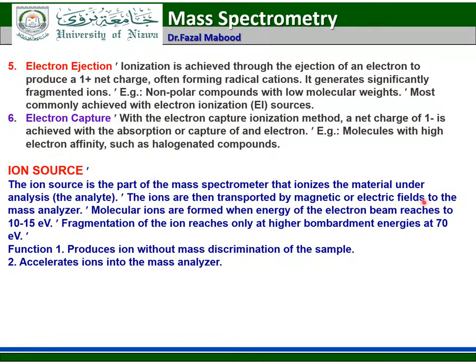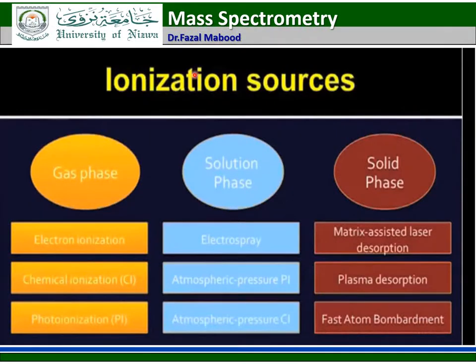Molecular ions are formed when the energy of the electron beam reaches 10 to 15 eV. Fragmentation of the ion occurs only at higher bombardment energy of 70 eV. The ion source produces ions without mass discrimination of the sample and accelerates ions into the mass analyzer. Based on the phase of the sample — gaseous, solution, or solid — different ionization sources are used. For gaseous phase: electron ionization, chemical ionization, and photo ionization. For solution phase: electrospray ionization, atmospheric pressure ionization, and atmospheric pressure chemical ionization. For solid phase: matrix-assisted laser desorption ionization (MALDI), plasma desorption, and fast atom bombardment ionization.